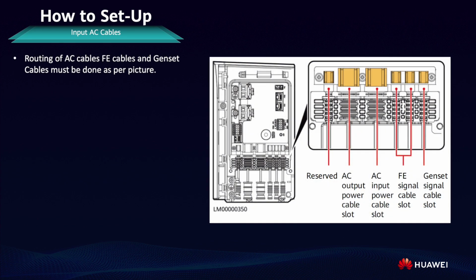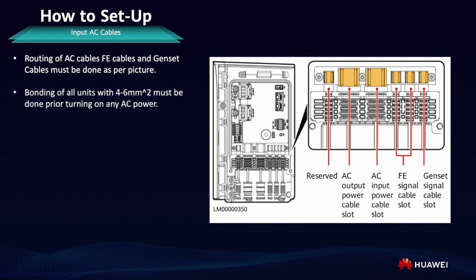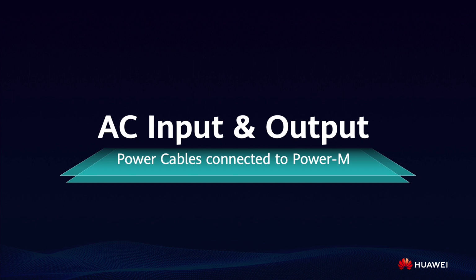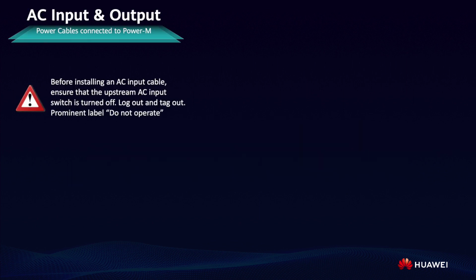Routing of AC cables, FE cables and genset cables must be done as per picture. Bonding of all units with 4 to 6 square millimeter must be done prior to turning on any AC power. Unit must be properly secured and installed as per suggested installation steps. AC input and output cable. Power cables connected to the power M. Before installing an AC input cable, ensure that the system AC input switch upstream is turned off.